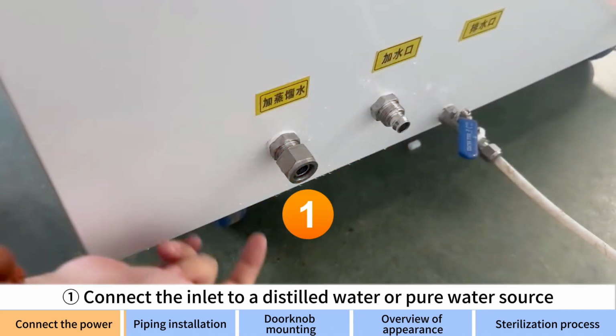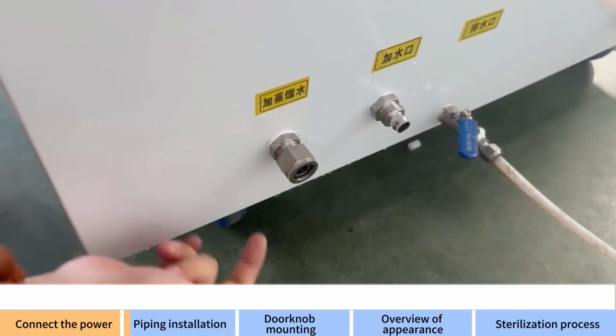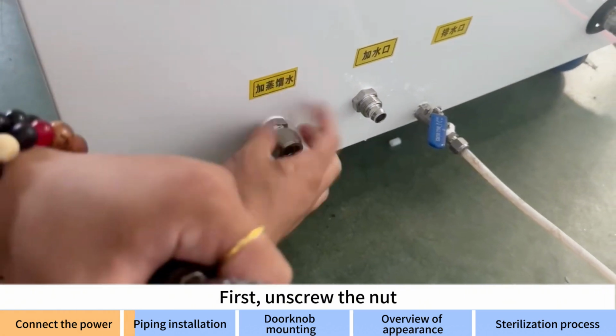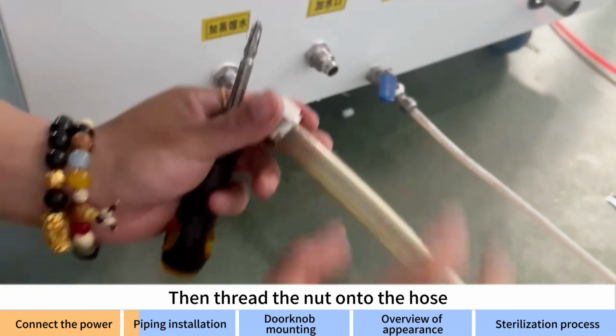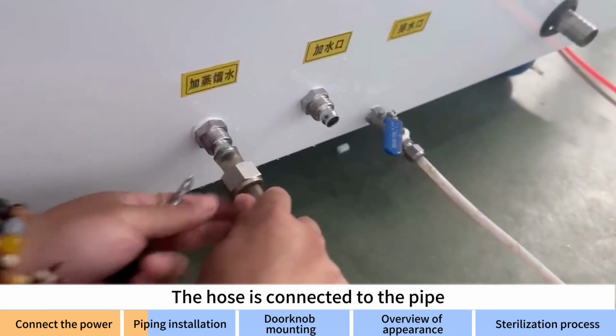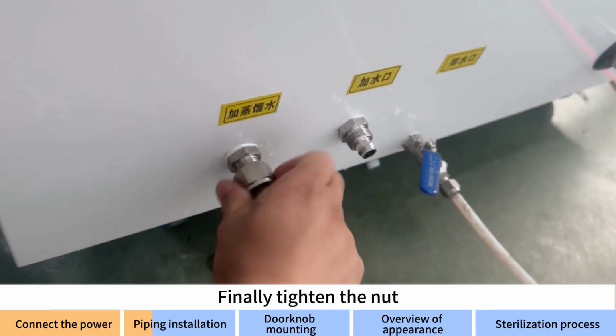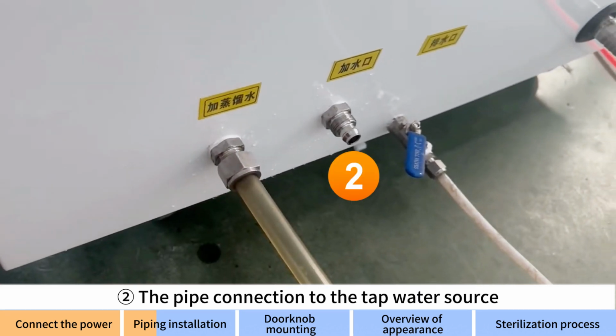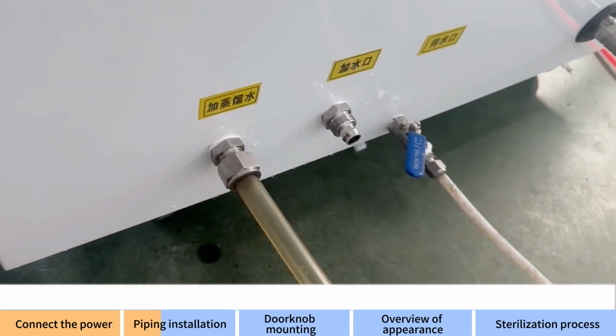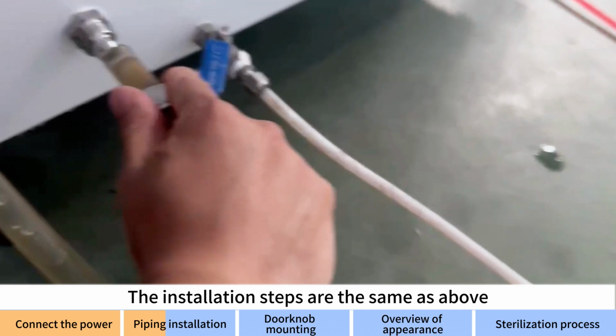Connect the inlet to a distilled water or pure water source. First, unscrew the nut. Then thread the nut onto the hose. The hose is connected to the pipe. Finally, tighten the nut. The pipe connection to the tap water source. The installation steps are the same as above.